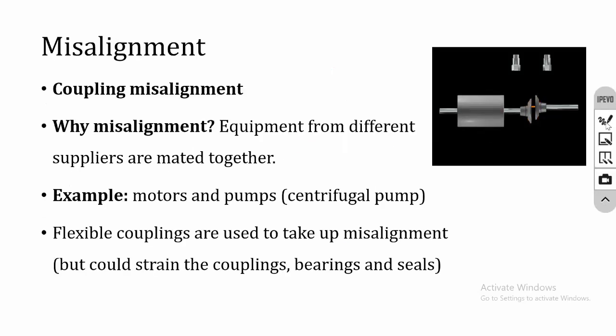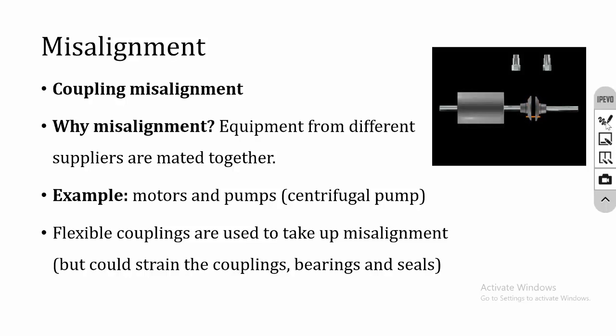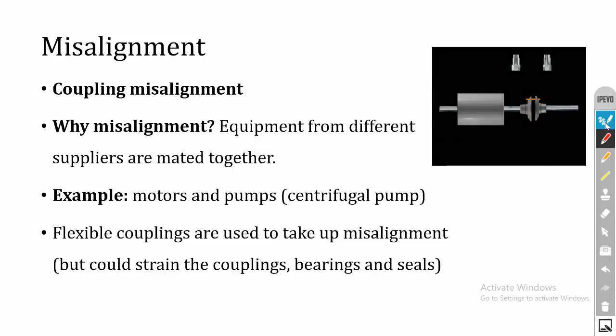The second machinery fault is misalignment. In general, pump shafts are fitted to motors using a coupling. If both shaft axes are not collinear, it will produce misalignment, and this misalignment will vibrate the system. You can see in the animation that both shafts are parallel but not collinear. The reason for misalignment is that different machines are purchased from different suppliers and are not uniform. For example, a pump from one supplier and a motor from another — we fix the shafts using a coupling, and if they are not perfect, that produces misalignment.